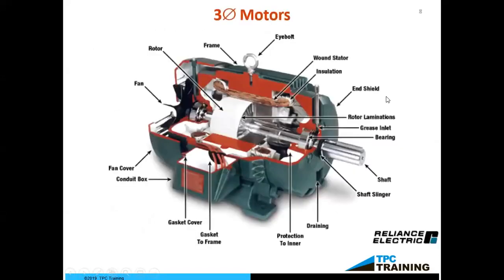Here we can actually see a cutaway version of the motor. What I really want to impress upon you is right here is that stator winding, where you can see my cursor moving. And then you can see the rotor. There might be a 16th of an inch gap there, but they're very close to each other so that we can maximize the power of that magnetic field. And how well do we maximize that power? Well, if this motor was a 1 horsepower motor, let's say, maybe on a pump for a swimming pool, the only force that's turning this rotor is the force of magnetism.